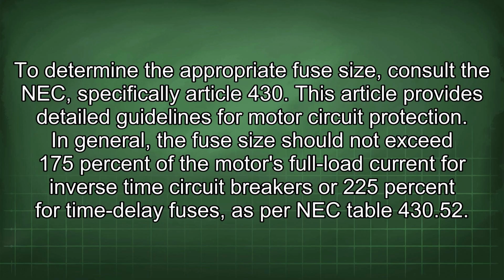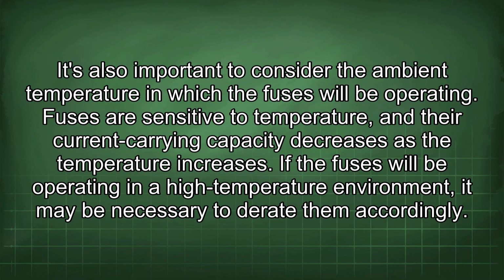In general, a fuse size should not exceed 175% of the motor's full load current for inverse time circuit breakers or 225% for time delay fuses, as per NEC Table 430.52. It's also important to consider the ambient temperature in which the fuses will be operating. Fuses are sensitive to temperature, and their current carrying capacity decreases as the temperature increases. If the fuses will be operating in a high-temperature environment, it may be necessary to derate them accordingly.